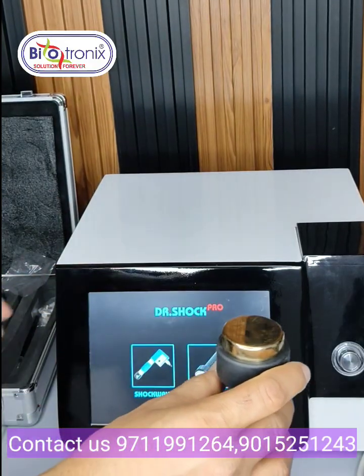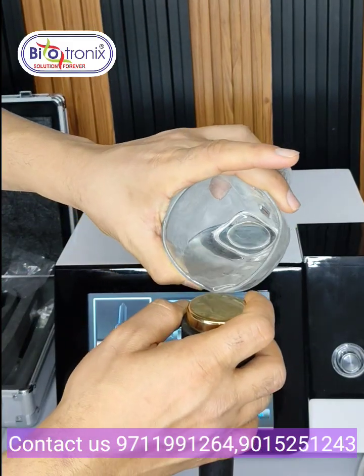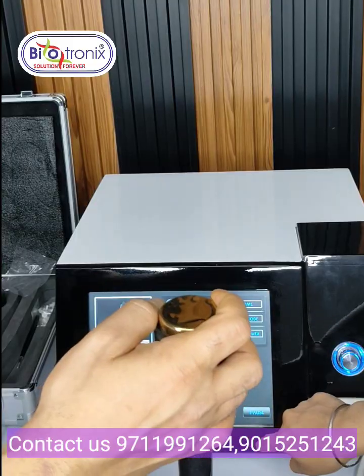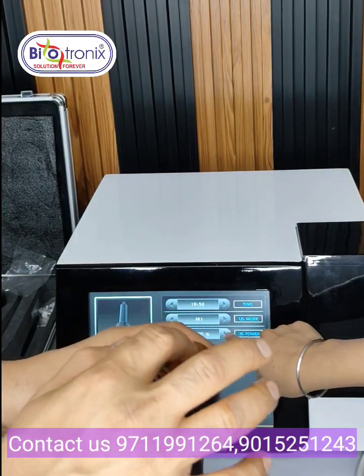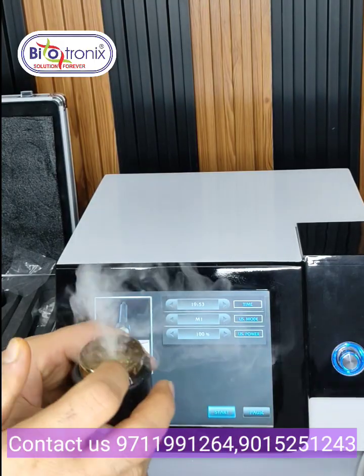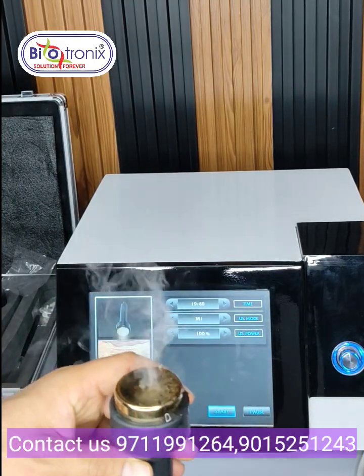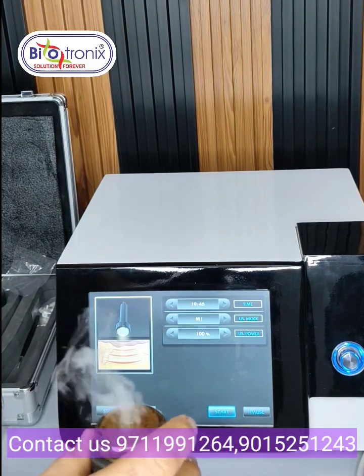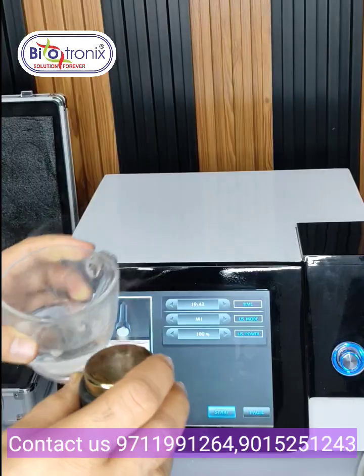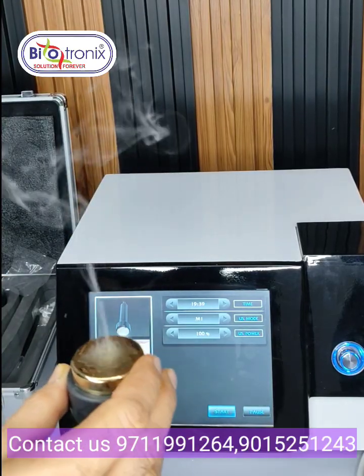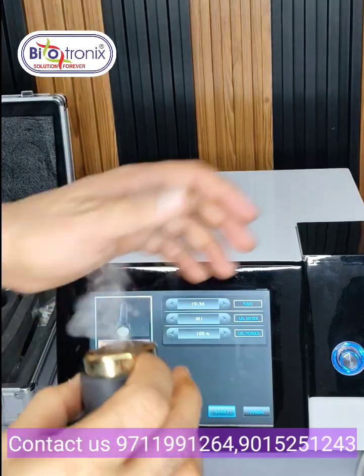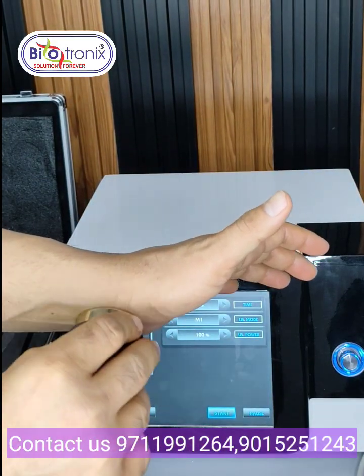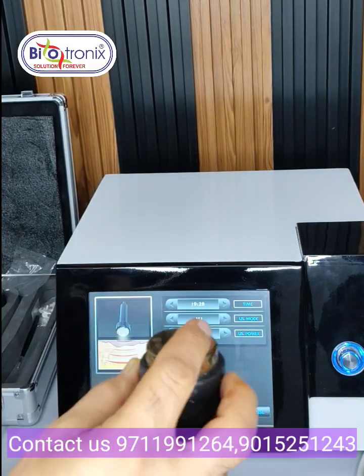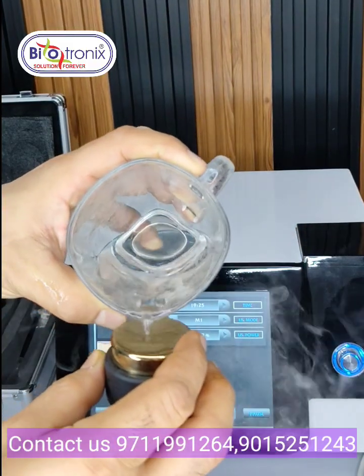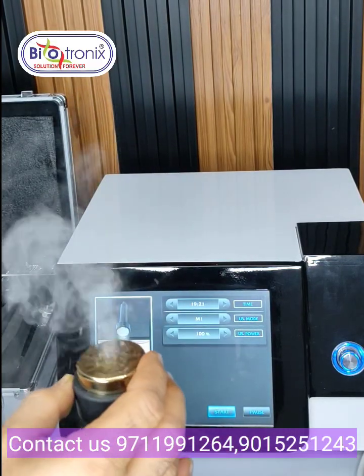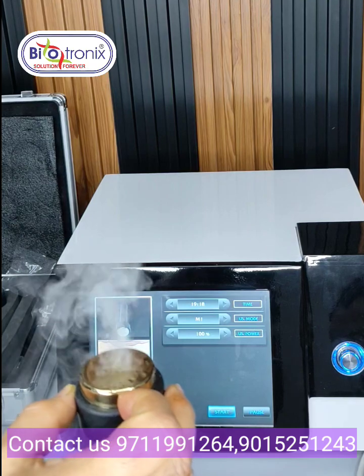Now I am putting some water on the ultrasound. I have entered the ultrasonic section. Now I will start it. You can see as I am increasing the intensity, the water is getting evaporated. Intensity is maximum, so don't use the ultrasound without contact of body or water, because that may damage the crystal in the air. So always use the ultrasound with some water on it for testing, or with contact of the body like this. Keep on revolving. If you use it without contact and intensity is maximum, that crystal may be damaged and the applicator will become faulty.